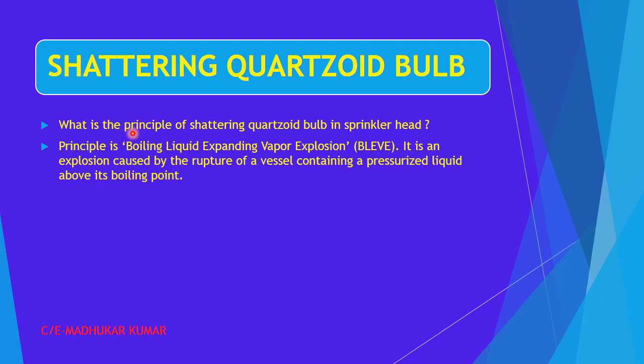Now we are going to see how this quartzoid bulb operates. So what is the principle of operating these bulbs? The principle is BLEVE, boiling liquid expanding vapor explosion. It is an explosion caused by the rupture of a vessel containing a pressurized liquid above its boiling point. So basically, there is a little gas space left, and when the temperature rises, the liquid will expand and pressurize the bulb and further rupture the bulb.